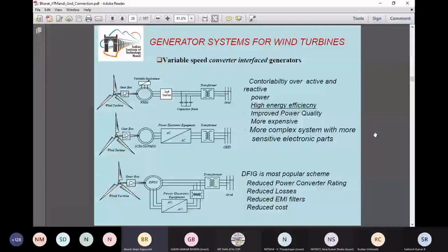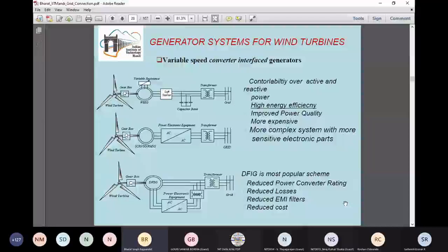Now see the middle scheme. The middle scheme consists of a generator made up of either a squirrel cage, or a permanent magnet, or a conventional synchronous generator. But converters are connected between the grid and the stator of the machine. This power electronic equipment performs an AC to AC conversion, where the AC input side is of some voltage and frequency, and it is converted, generally by a back-to-back power electronic converter, from AC into DC; there is a DC link, and then this DC is converted back into AC, which is suitable to be synchronized with the grid, having the nominal frequency and nominal voltage. As they are processing the stator power, these power electronic equipment are of the same rating as the system.